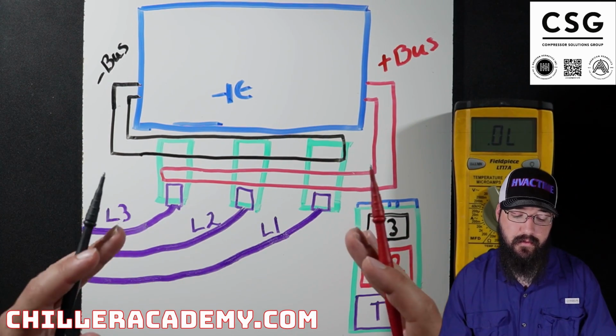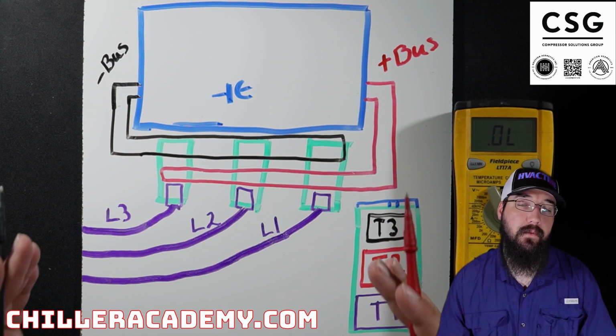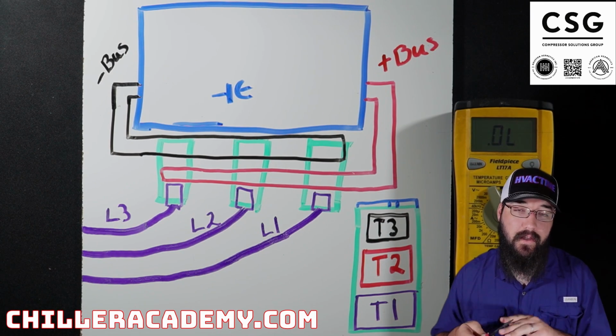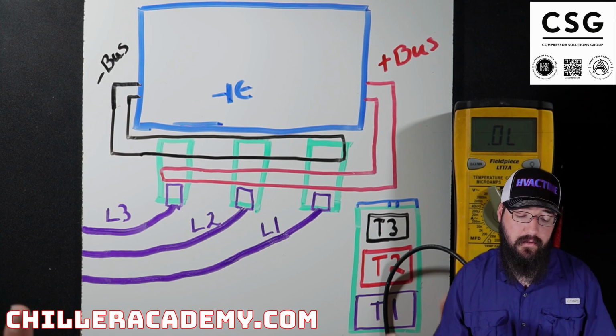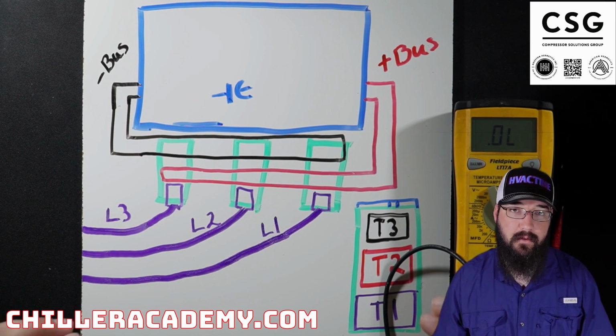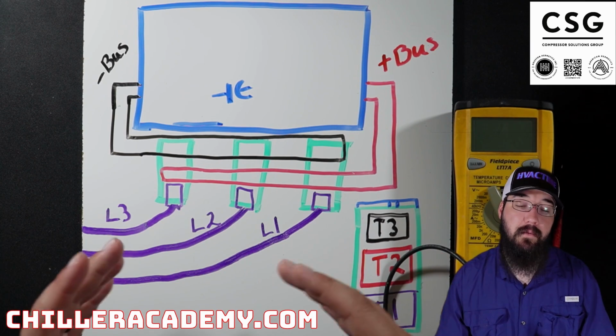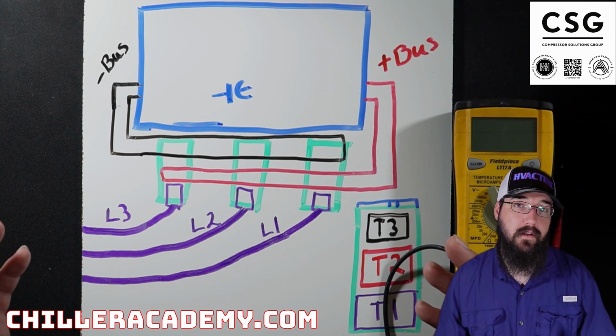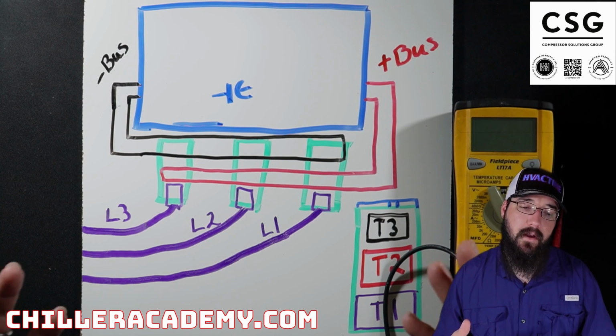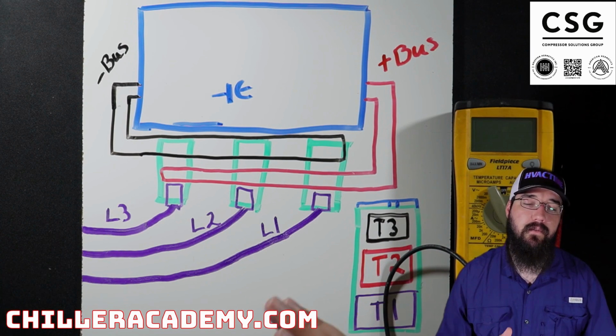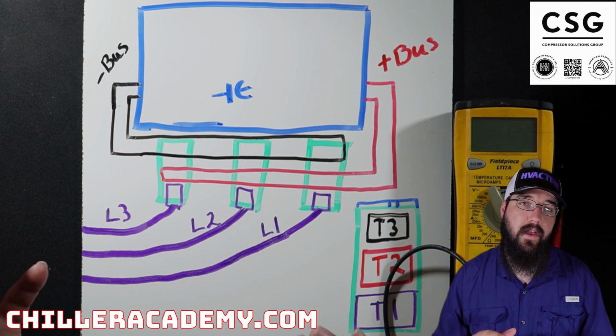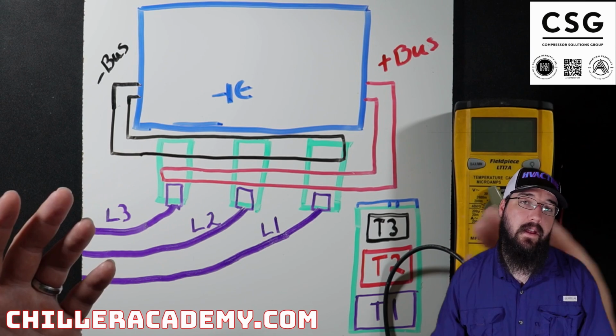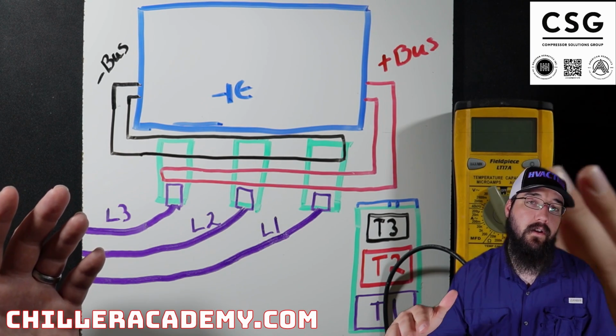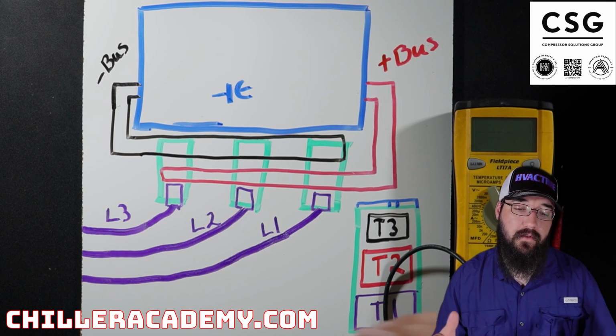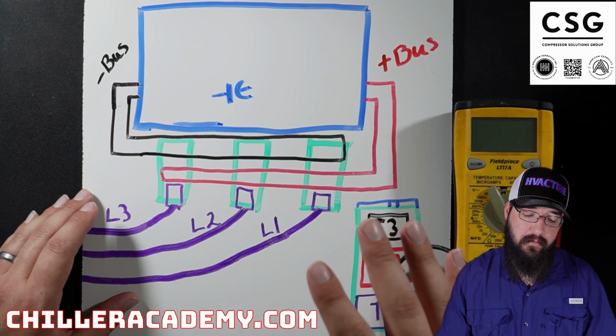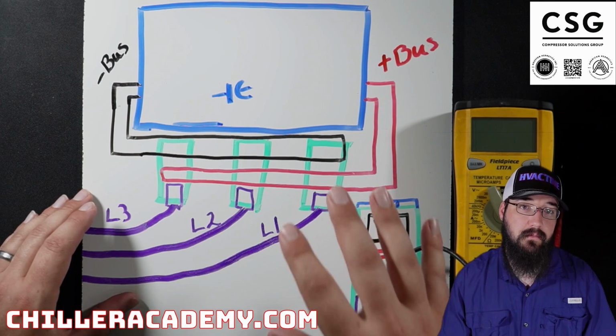That is the test procedure to go terminal to terminal to see what the condition of the internal silicon is on these SCRs. Keep in mind, these particular SCRs are only used on the Viper drive assemblies, which are your little bit older drives. If you open it up, you might see a Hyperdrive. One of the ways to tell the difference, there are several, is that they do look different, but we don't have these SCRs. We have IGBT modules that do our rectification coming in, and IGBTs doing our inversion, going back out to the motor. So it's one of the things to just be aware of, and I want to be real specific on which drive assembly we're referencing here.